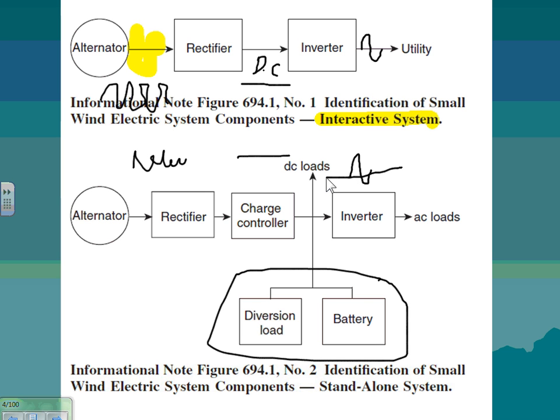What's the diversion load? There are two reasons for the diversion loads. Diversion load number one is as you charge your batteries, you control the charging so they don't explode. They have a diversion load, so if you're charging too much and you don't want to overcharge the battery so it doesn't explode, there's a control system that diverts all this current directly to a bunch of resistors, believe it or not. And you convert that energy into heat. So it's part of the control of the charging mechanism for the battery.